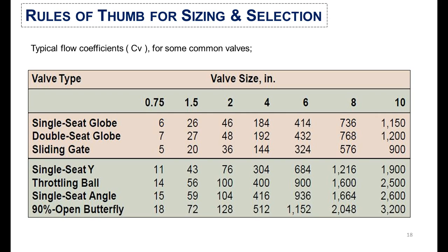Here are typical flow coefficients — Cv values — for some common valves. For example, if there is a single seat globe valve and your calculated Cv is 26, then the valve size will be 1.5 inches. Similarly, with other valve types, you can identify the valve size corresponding to your calculated Cv from the provided table.